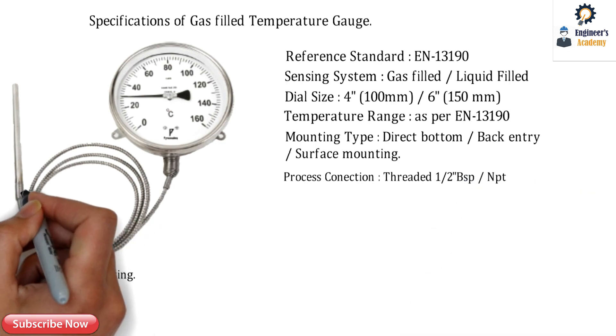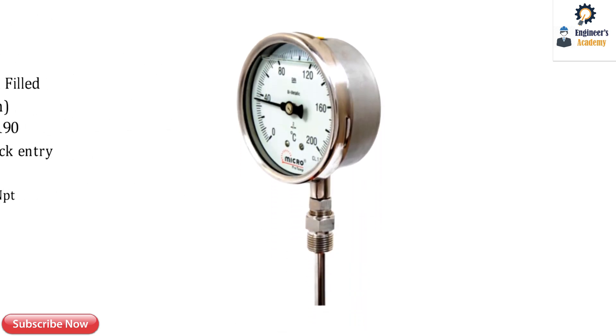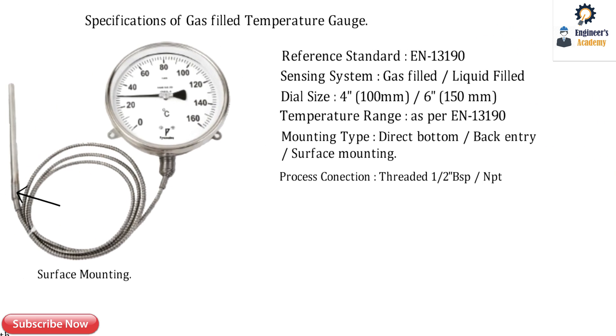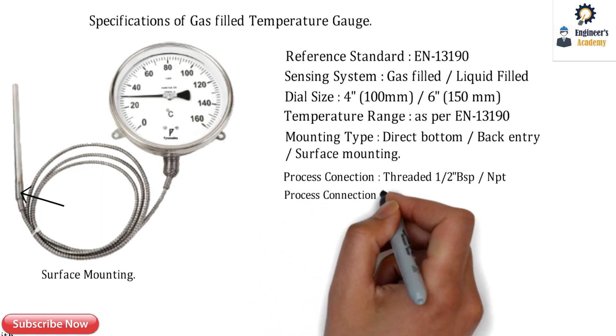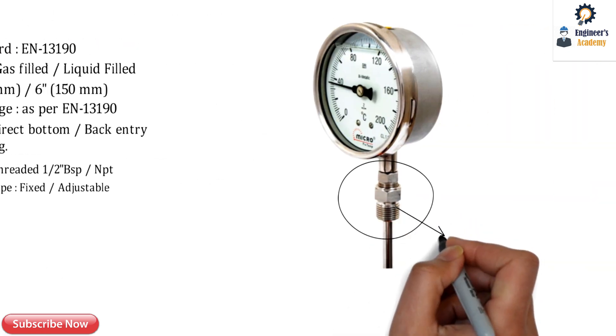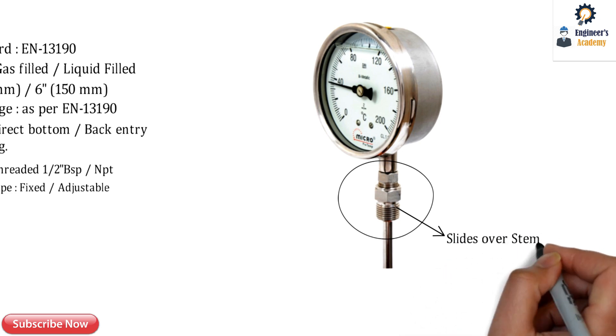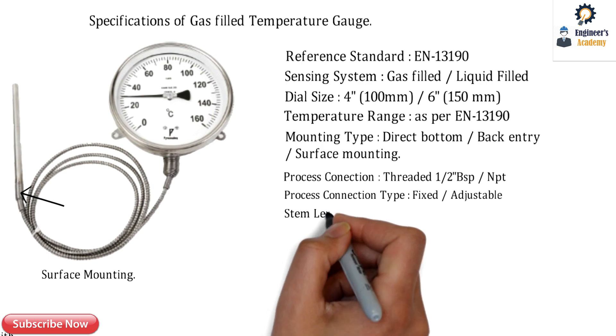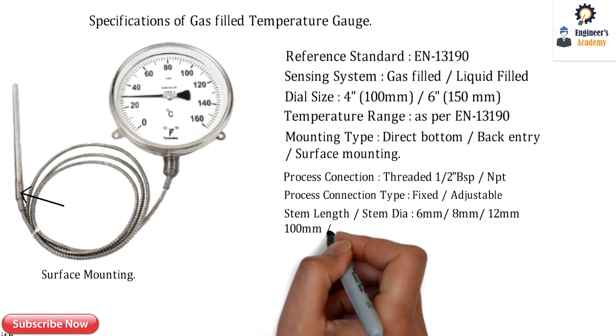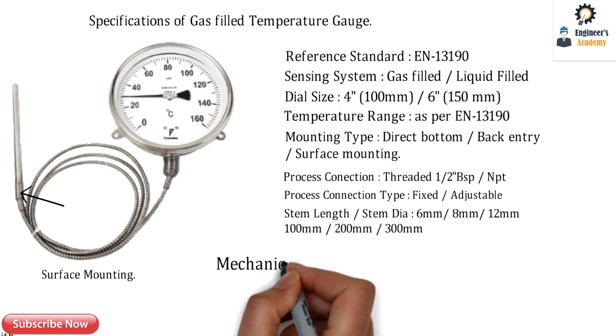Here you can see the ACF — the adjustable compression fitting — which is the process connection of the gauge. The process connection type can be fixed or adjustable. The ACF slides over the stem of the temperature gauge. The stem diameter can be 6mm, 8mm, or 12mm, whereas the stem length varies as per the requirement.